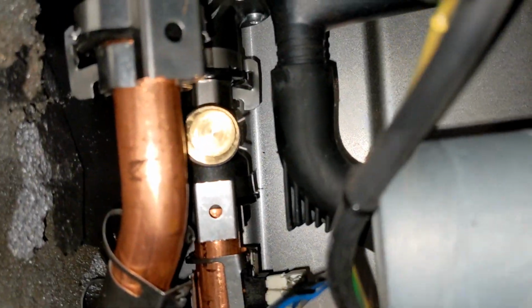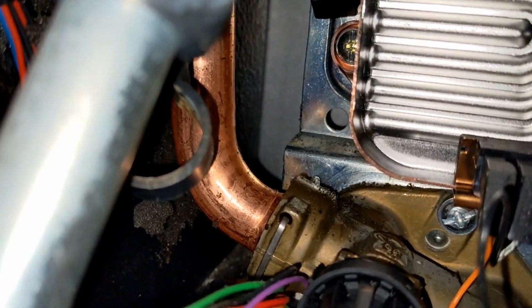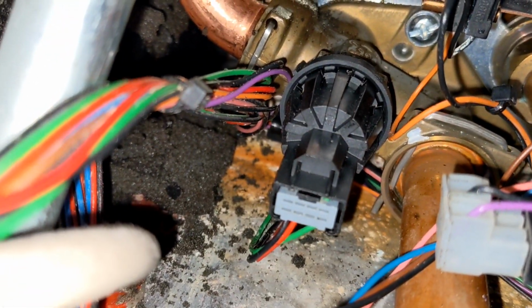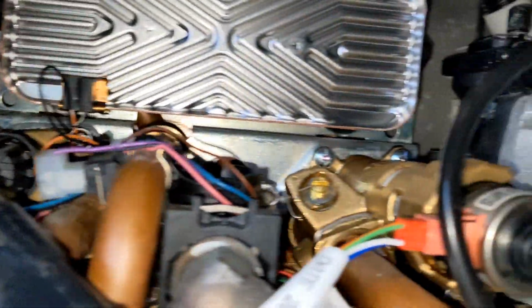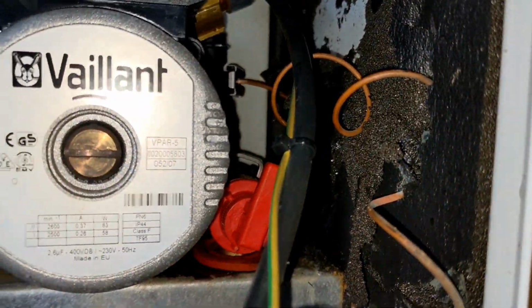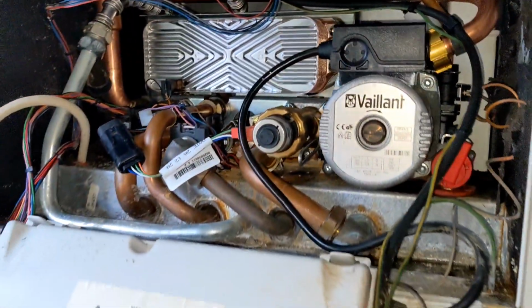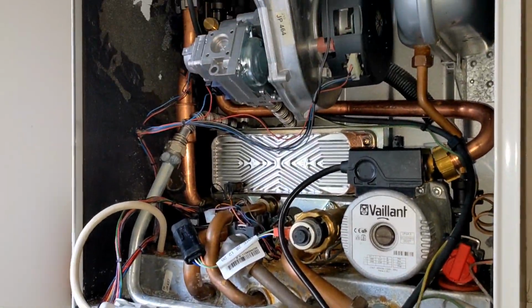The main thing is we've got no leaks coming off of there. So now that we haven't cracked the main heat exchanger, that connection's all good. Pressure sensor connection's all good. PRV's all good. Just purging it now. We should be good to go.